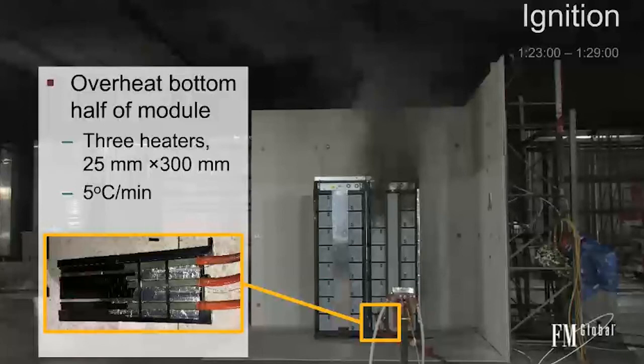combustion. There are other ways to do this, and certainly there are more savvy ways to do this. One of the ones I've seen is people will open up the module and put small heaters against individual cells, and then they'll cause an ignition, and that'll propagate from one cell to the next within the module. You could also do nail penetrations. You could do overcurrent. So there are a lot of ways you can cause a battery to go into thermal runaway. Ultimately, all of these things are just heat. So for simplicity in this test, all we did was strap 3 heaters to the module, and then just let everything else take care of itself. Because of that, this isn't the most efficient way to cause ignition.